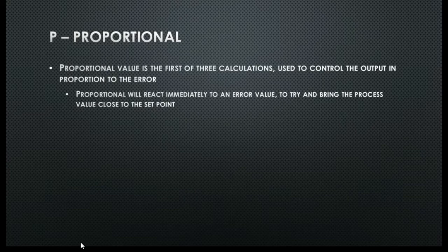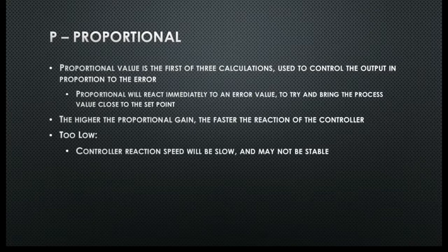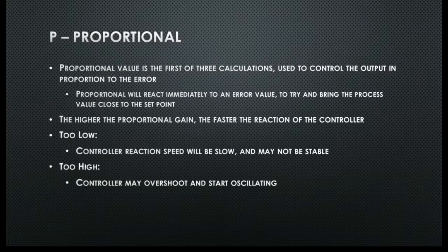Now it's time to look at the P, the I, and the D separately to see how each one affects the output of the controller. The proportional value is the first of the three calculations and it's used to control the output in proportion to whatever the error value is. The proportional will react immediately to the error and tries to bring the process value up close to the set point. The higher the proportional gain, the faster the reaction of the controller. If we set the proportional too low, the reaction speed may be too slow and the controller might become unstable. If the proportional value is set too high, the controller might become unstable, overshoot the set point, and go into an oscillation.